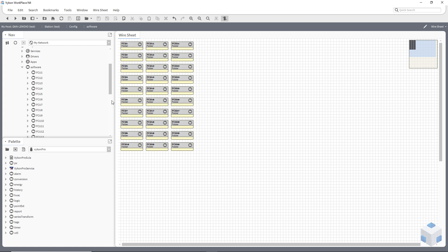I've got a lot of pseudo points here within folders, so you can see fan coil units from 1 to 30. What I want to use this block for is to actually go and look at every single point within this folder, say a heating valve, and look at the demand. So if I have a heating demand of over a set amount of percentage over the floor, I then want to enable the heating plant.